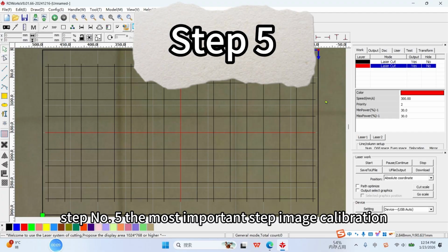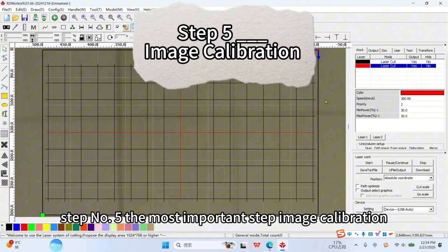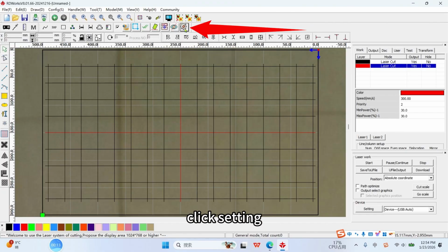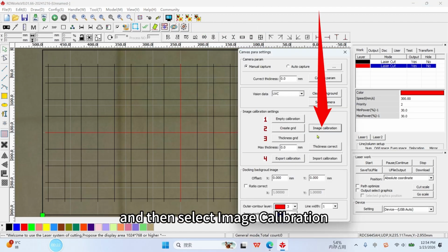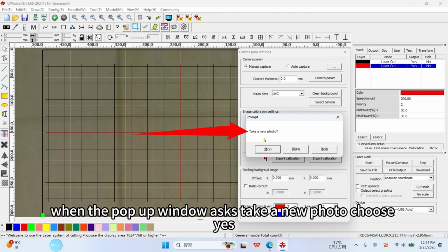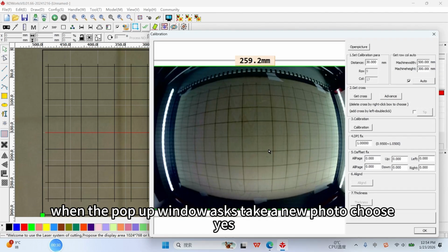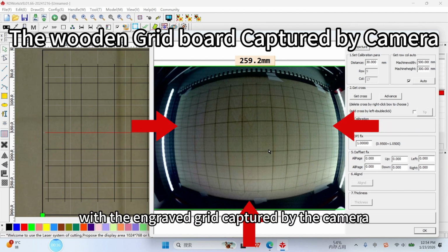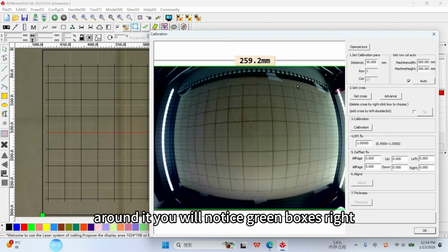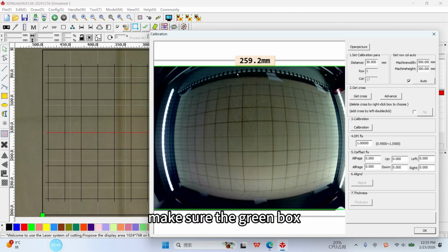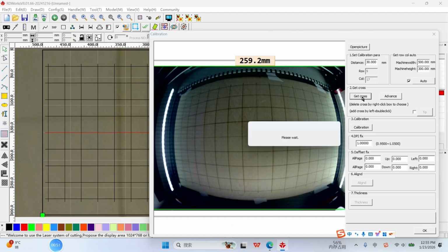Step number 5, the most important step, image calibration. Click Setting here, and then select Image Calibration. When the pop-up window asks to take a new photo, choose Yes. So now you will see the wooden board with the engraved grid captured by the camera. Around it, you will notice green boxes, right? Make sure the green box frames the entire wooden board. Then click Get Cross.